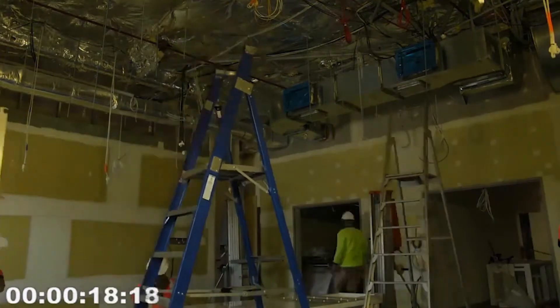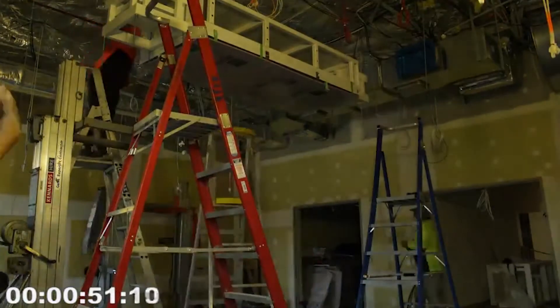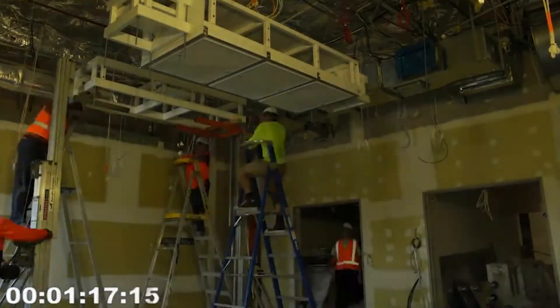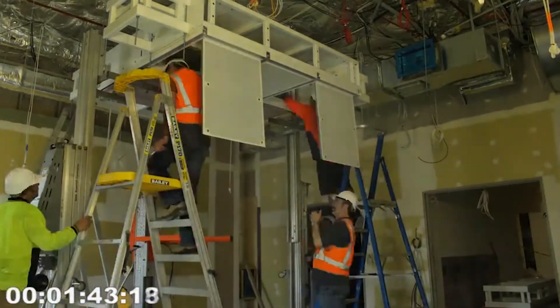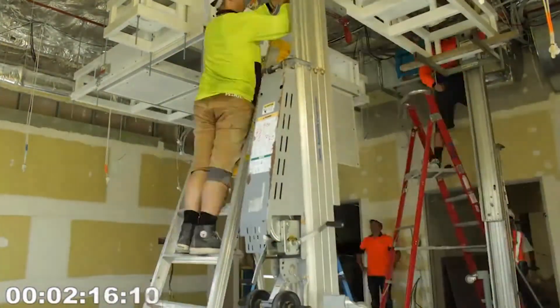The physical installation of the airframe is much quicker — from an installation perspective it is superior to a traditional operating theatre. I was shocked at how quickly airframe went in. It was a very fast install. Airframe was up in the ceiling inside three hours, whereas a traditional system would take a number of weeks to install.